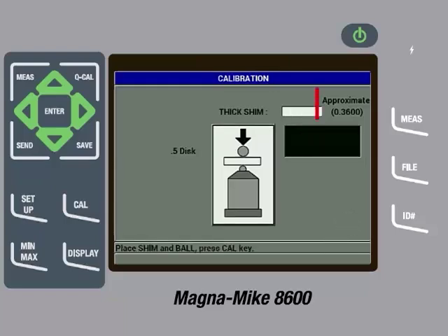The gauge will then ask for a thick shim and call out an approximate thickness value for the thick shim to use. The thick shim called out for the disc target being used is 0.3600, or if you are using metric units, it would be 9.144. The next step would be to insert the disc into the slot on the top cap of the thickness reference standard and then place the fixture on the probe tip. Then, gently pull down on the sides of the fixture to ensure the shim is in contact with the probe tip. The instrument will start displaying a thickness value. Once the reading is steady, press the Cal key. Then use the arrow keys to input the precise thickness of the shim, which in this case is 0.3600, or if you are using metric units, it would be 9.144. Then press the Cal key.